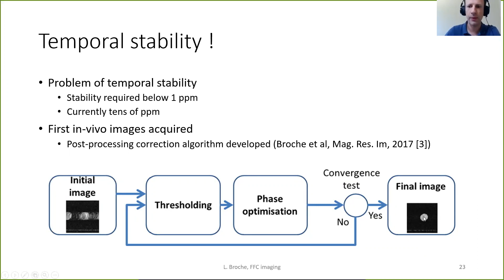Another problem we have with field cycling is radio frequency range. RF on the MRI scanners is typically in the range of 100 megahertz or above, and that makes it relatively easy to perform certain tasks. In particular, you can get radio frequency amplifiers and preamplifiers in that range quite easily. When you work between 1 and 10 megahertz, it's more difficult to get these kinds of devices. And you have also a problem.